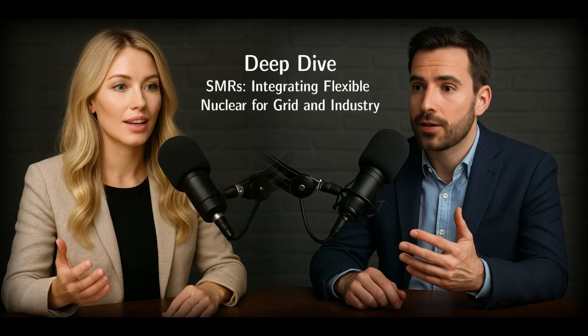Very fast. And voltage support? Reactive power? Robust capability there too. Plus or minus 40% of their rated power in reactive power. They operate with automatic voltage regulators, achieving a power factor from 0.85 leading to 0.95 lagging. That significantly boosts power quality and grid stability. So they can actively manage voltage levels. Exactly. Injecting or absorbing reactive power to keep voltage within the required limits.